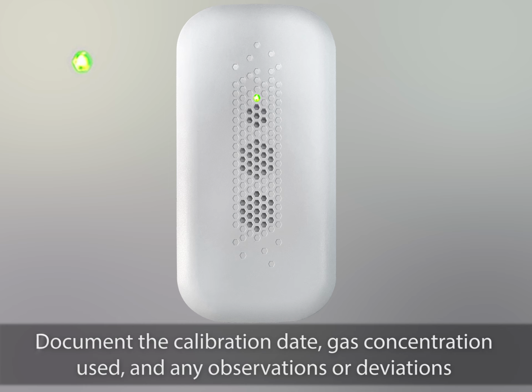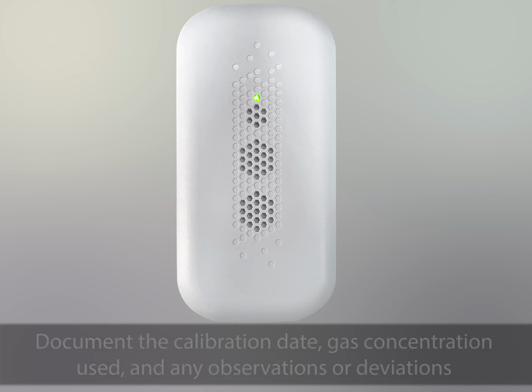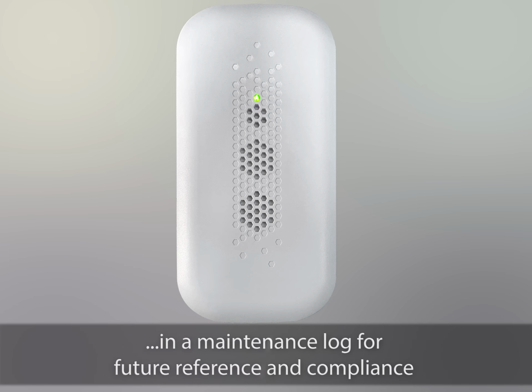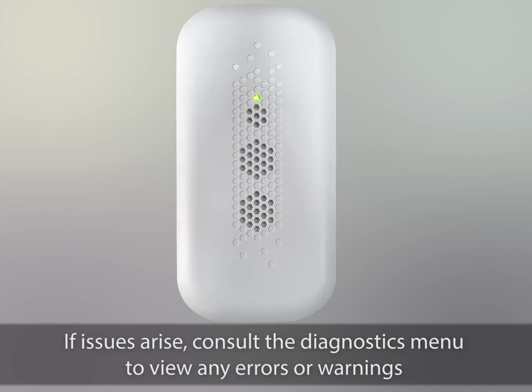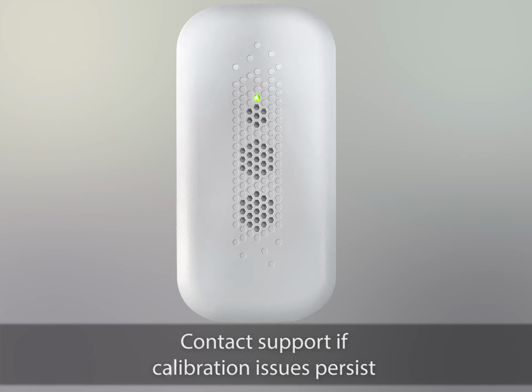Be sure to document the calibration date, gas concentration used, and any observations or deviations in a maintenance log for future reference and compliance. If issues arise, consult the diagnostics menu to view any errors or warnings, and contact support if calibration issues persist.